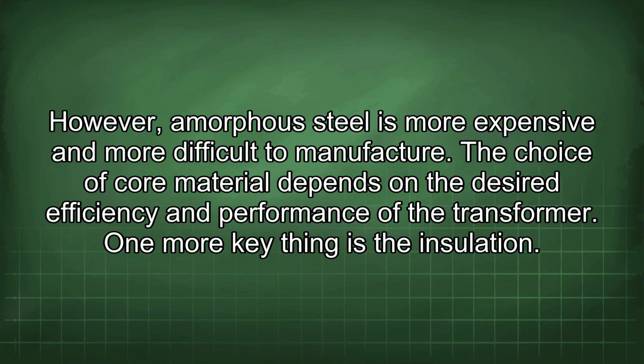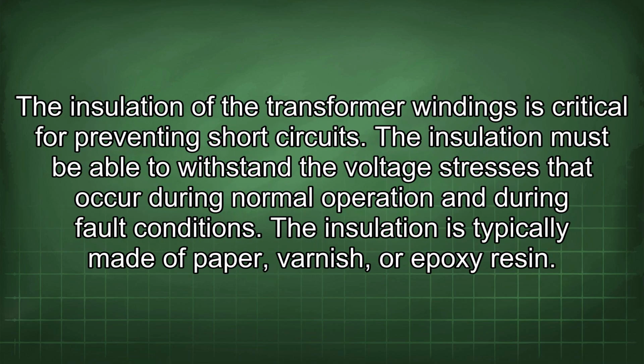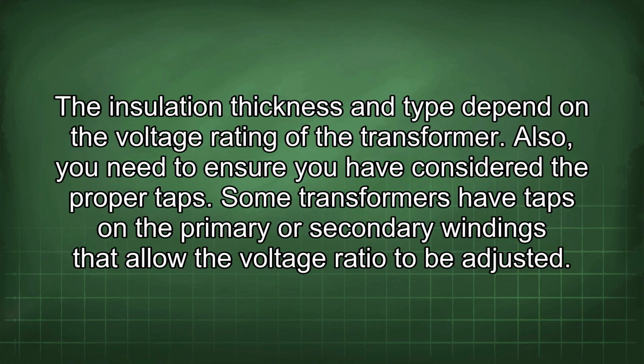One more key thing is the insulation. The insulation of the transformer windings is critical for preventing short circuits. The insulation must be able to withstand the voltage stresses that occur during normal operation and during fault conditions. The insulation is typically made of paper, varnish, or epoxy resin. The insulation thickness and type depend on the voltage rating of the transformer.